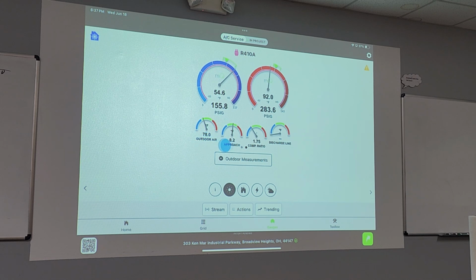Now we have outdoor air temp, approach, compression ratio. I don't have a discharge line clamp hooked up to this. That's why that's blank. That is an optional probe, unless you're on a heat pump, then it's called the vapor line, and then it's required. Indoor measurements: supply and return, dry bulb, and dew point. I prefer dew point. There is a setting in here that you can have it display dew point, relative humidity, or wet bulb, depending on your preference. I like dew point.